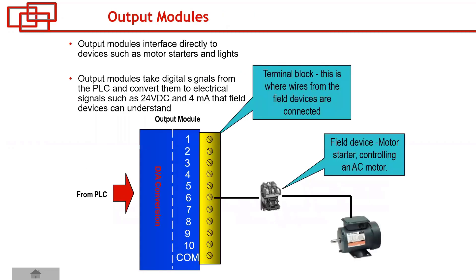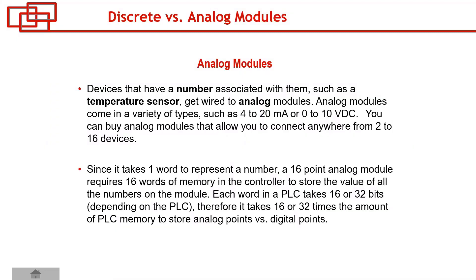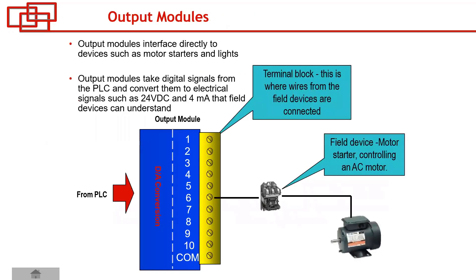Can you summarize why we need an output module, referencing the reason we need an input module? The input module receives signals from the field; the output module is needed for the PLC to send commands and direct actions. The PLC logic is digital — it's zeros and ones — and to send a signal to the field it needs to be converted, whether it's 24V DC, a dry contact, or a 4–20 mA signal. So it needs to be converted from digital to analog — digital to the standard electrical signal. That's the right description.